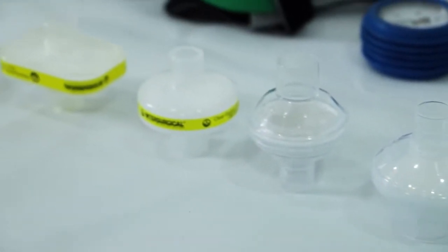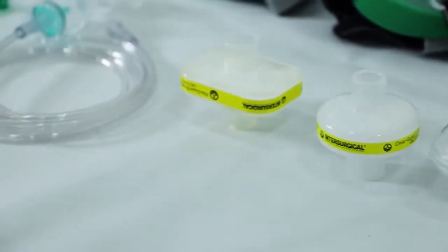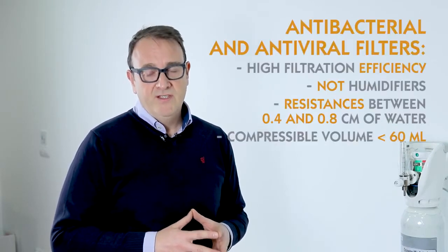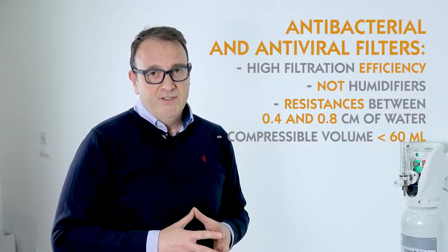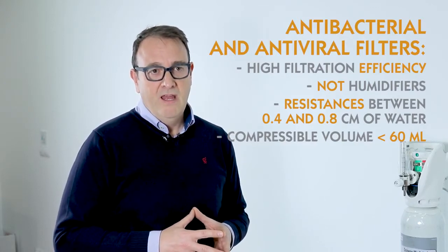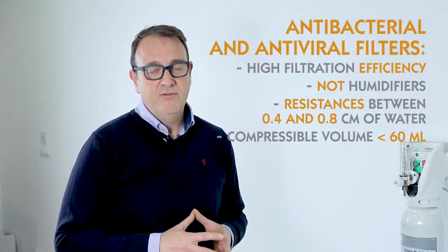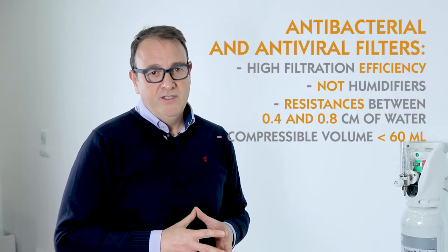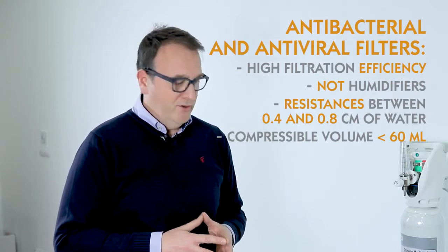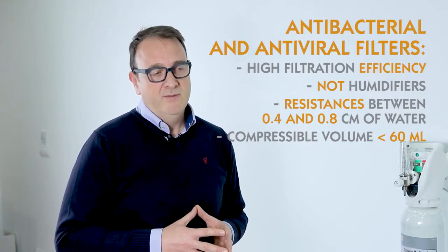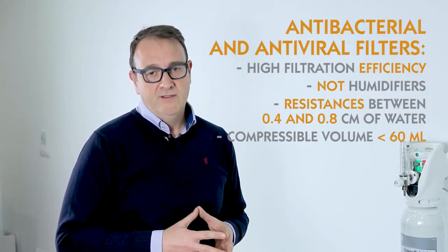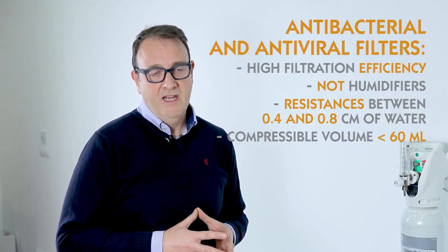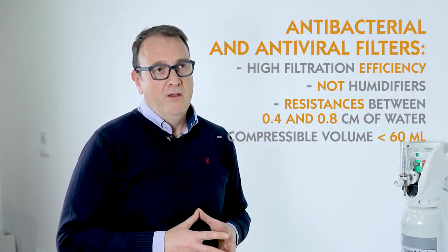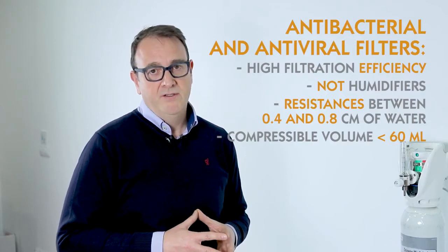We have 5 filters. It's important to remark that these are not heat and moisture exchangers, they are only filters, so they are not going to add any humidification to the circuit. The main characteristics of these filters are that they have low resistance and a low dead space. This is really important because they do not interfere with the CPAP system. The low resistance range is between 0.5 to 0.9 centimeters of water, and the dead space that they can add to the circuits is very low, less than 60-70 milliliters.